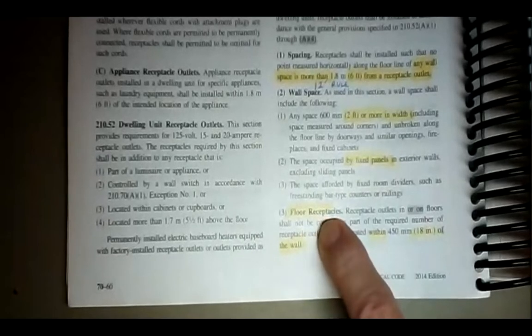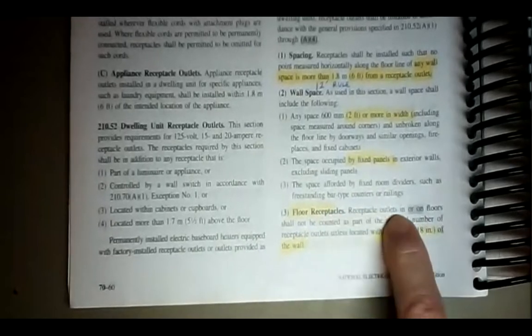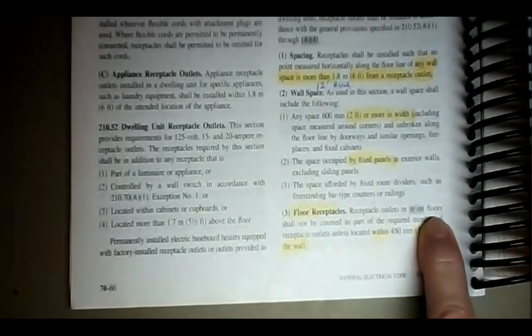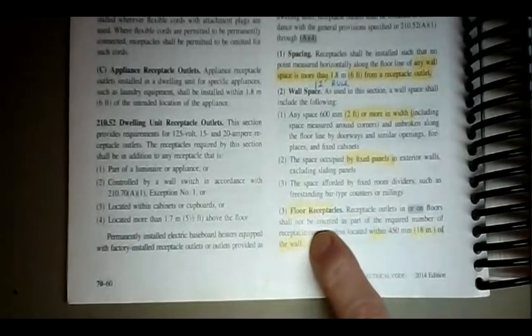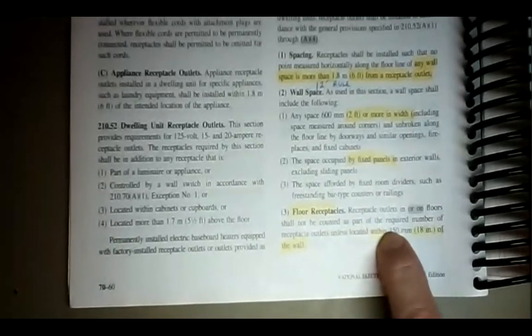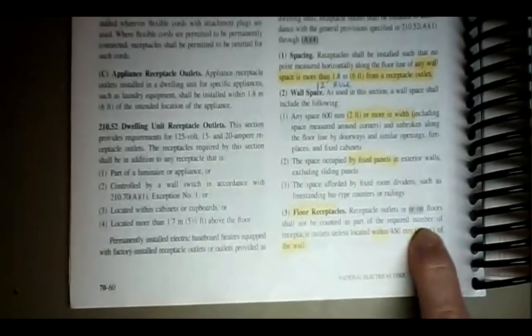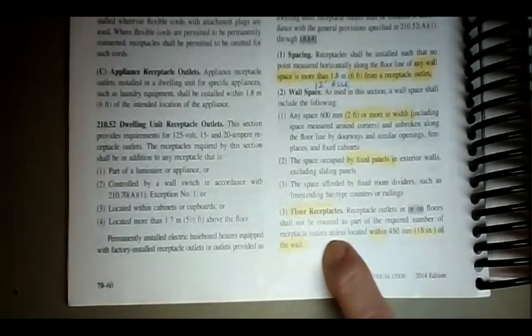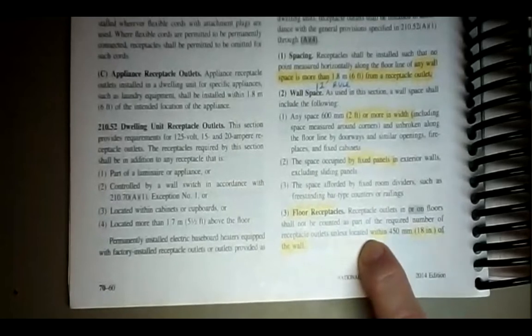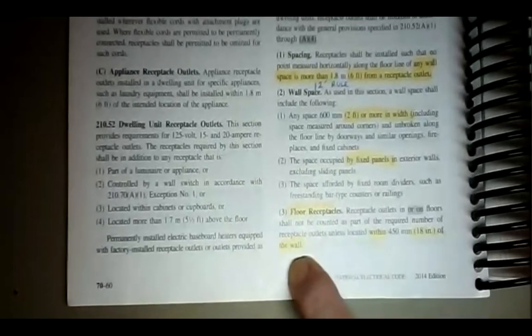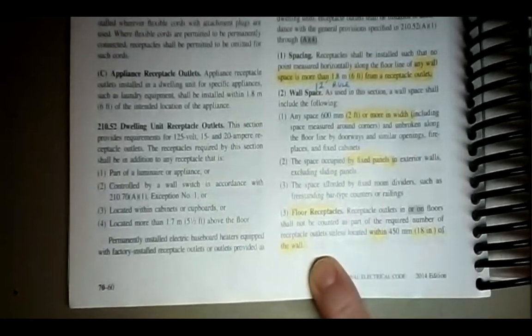Floor receptacles: receptacle outlets in or on floors shall not be counted as part of the required number of receptacles unless located within 18 inches of a wall.